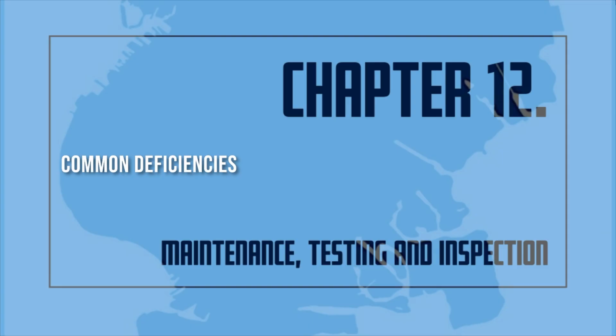The certificate of fitness holder shall assume that the system being inspected is installed in accordance with the New York City Building Code in effect at the time of installation. The certificate of fitness holder is to report those items of change that impact the system components regarding compliance with any retroactive requirements, the condition of the water supply control valves, water and air levels in reserve tanks and condition of same, unusual changes in water supply or system pressures, condition and accessibility of control valves, fire department connections, clearance around sprinkler heads, accessibility of the curb valve box, system control valves, required signage, attachments to piping other than system components, misaligned piping due to impact, missing pipe hangers and supports, excessive operation of pressure relief valves, easily recognized recalled sprinkler heads, and visible leakage.